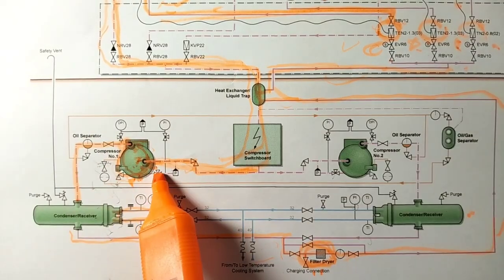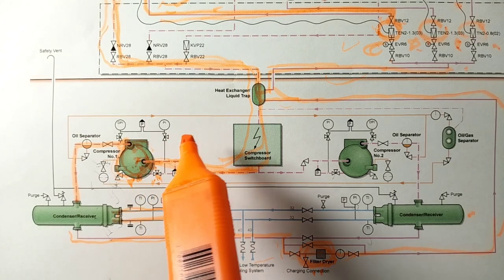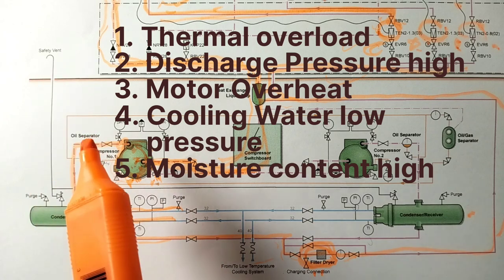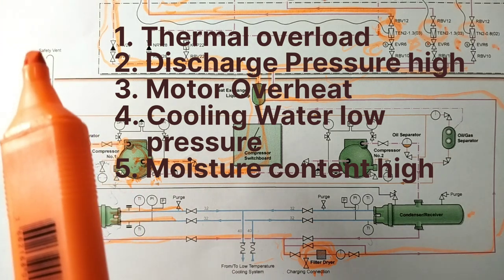These compressors are protected by a few trips and alarms: thermal overload, discharge pressure high, motor overheat, cooling water low pressure, and moisture content high. That's all guys — I will wrap up this video. I hope you have learned something from this video, and if you found it informative and valuable, please like and subscribe to my channel. Don't forget to click the bell icon. Thank you so much — till then, see you, take care, goodbye.